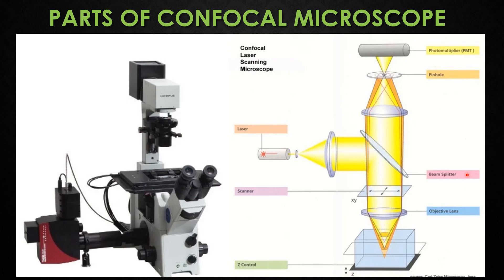The stage is a platform that holds the sample and allows it to be moved in order to scan the sample. The z-control allows the user to focus the laser beam on any focal plane within the specimen. The motorized z-stepper allows movement in the axial direction in small steps of approximately greater than 10 nanometers with high precision.